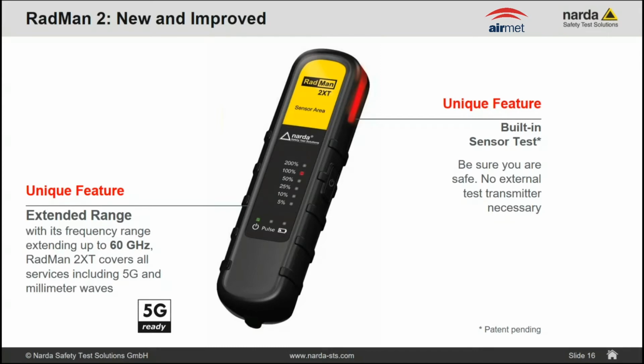These diodes might burn in the worst case if it's above the destruction limit, and then if the diode is burned, you will have an open connection, and again this open connection is being checked during the boot phase of the instrument. So we would expect that more than 99% of all these instances will be covered by this internal check.